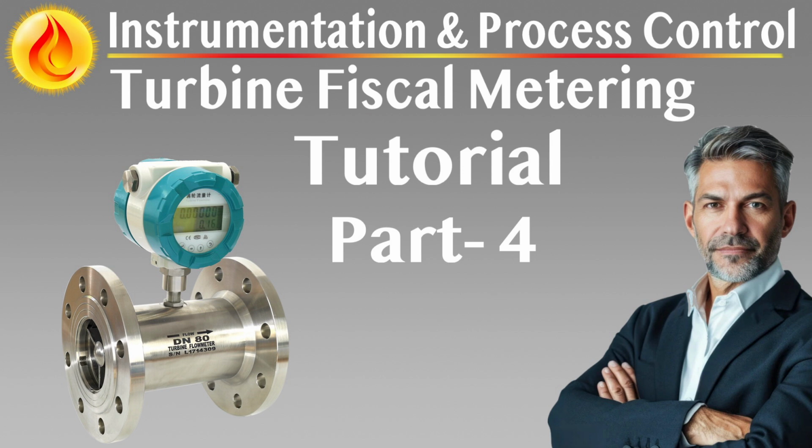Monitoring and control system, digital oversight and distributed computation for fiscal metering. Stream microcomputer, dedicated meter run control, and real-time computation. Each metering stream must be controlled and monitored by an independent stream microcomputer. This unit is dedicated solely to functions associated with fiscal measurement and must not perform unrelated control or communication tasks. The stream microcomputer acts as the primary interface between the turbine meter, associated transmitters, and the overall station control architecture.